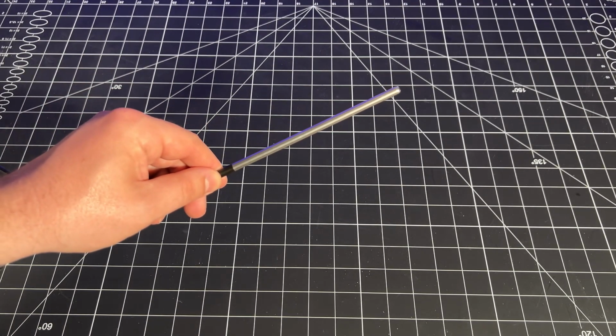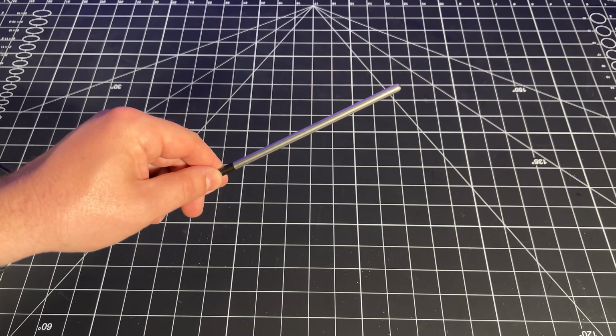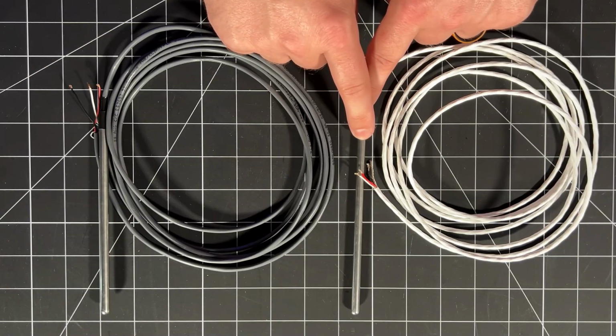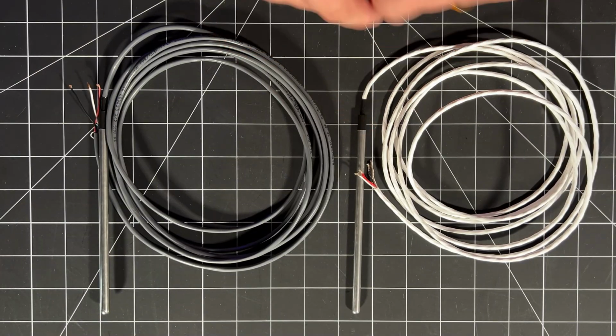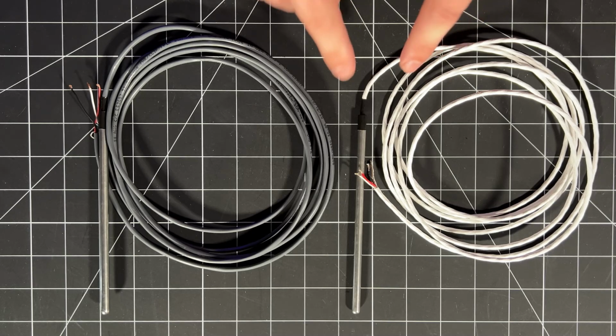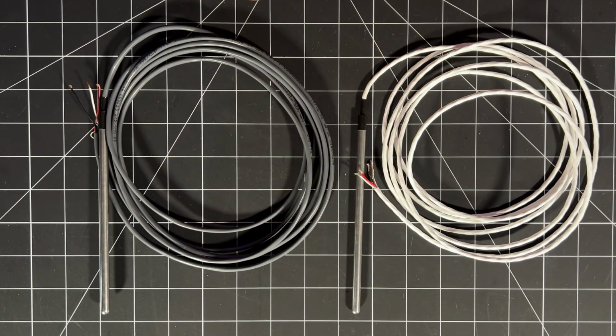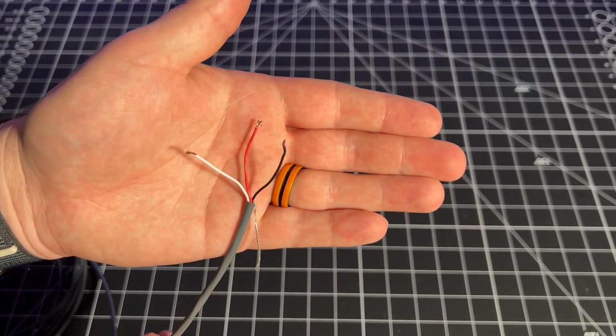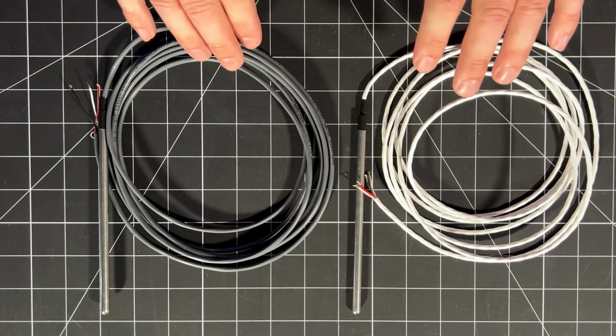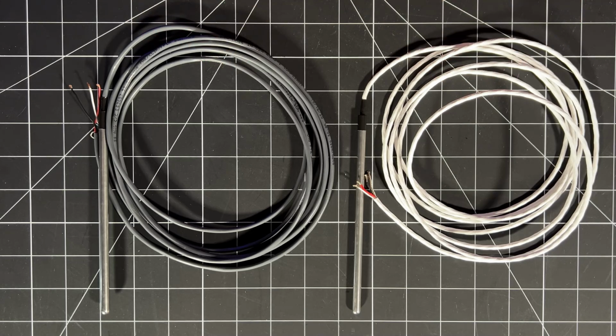The sensing element is in a stainless steel case to help prevent any corrosion or interaction with whatever you're measuring. And that case is 6 inches long and 1/4 inch in diameter. All of the electronics are inside that case, and they're encased in a waterproof potting compound. This means that this sensor is very, very durable. And because it's such a simple interface, it only has a 3-wire output. The wire is 3 meters long, so you can reach from whatever you're measuring to your acquisition system, and of course you can trim it to any length that you'd like.